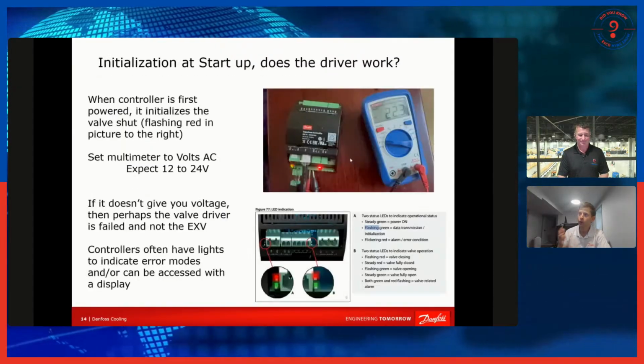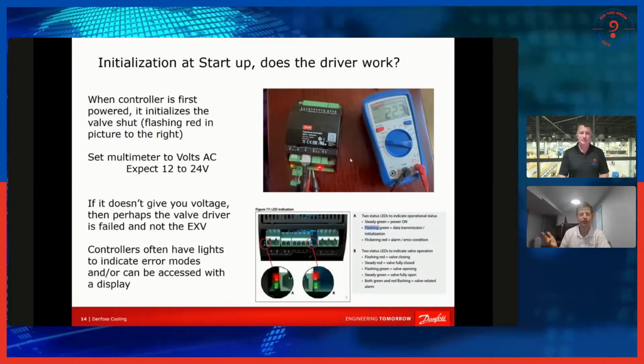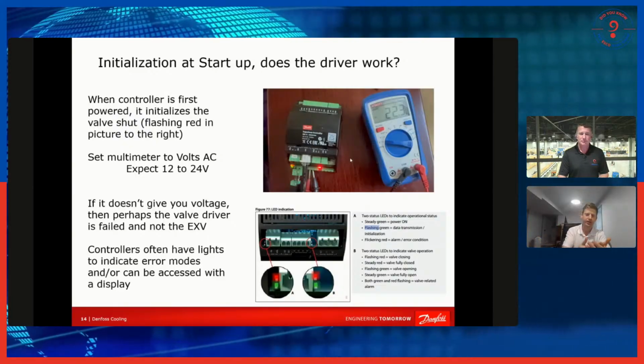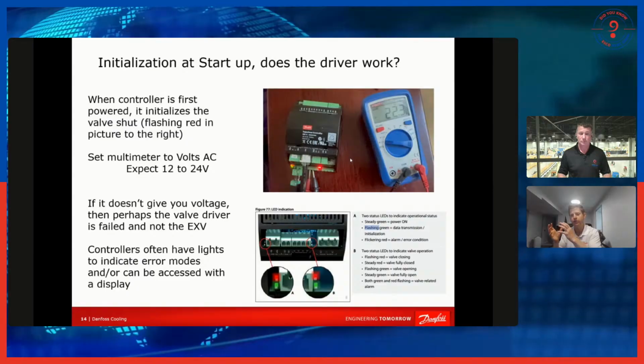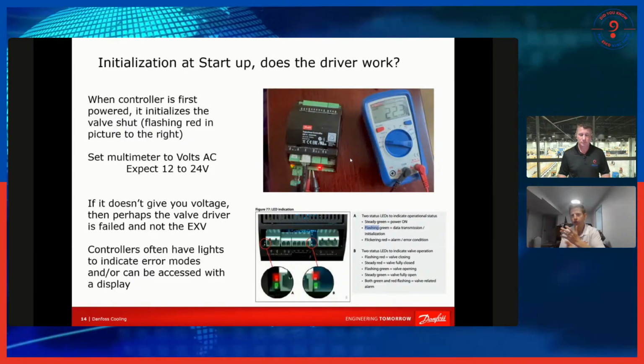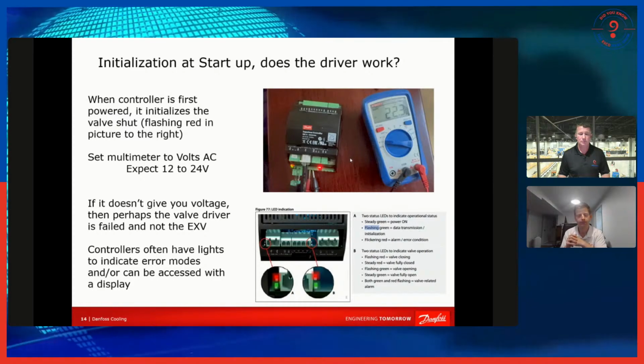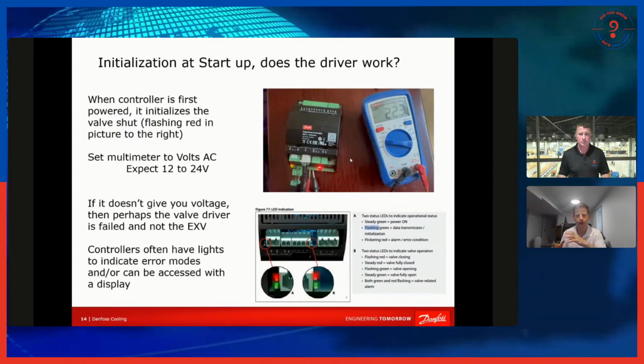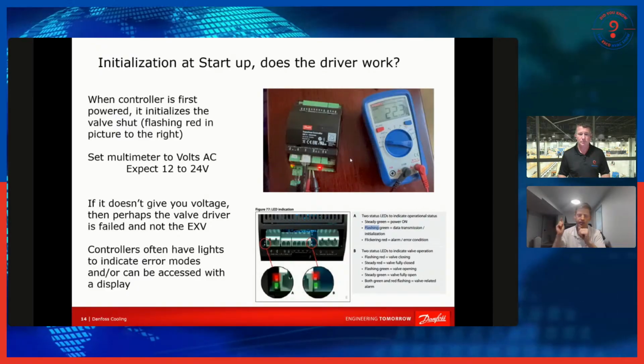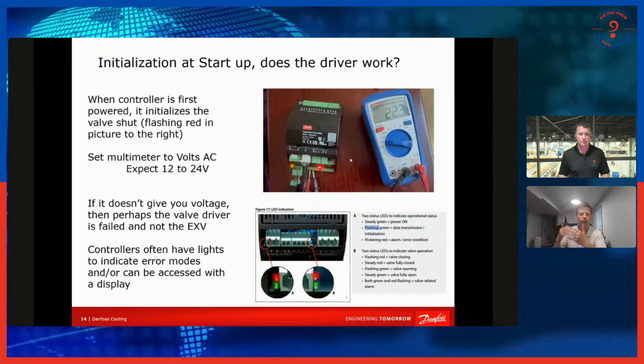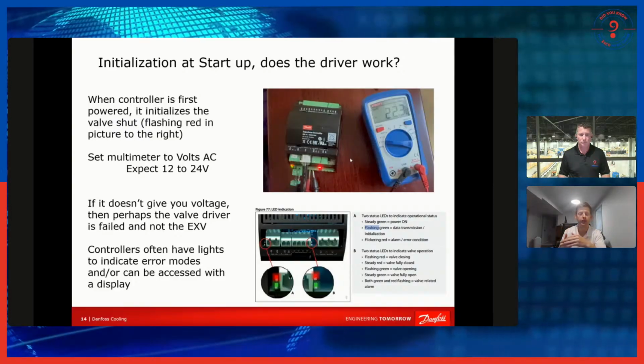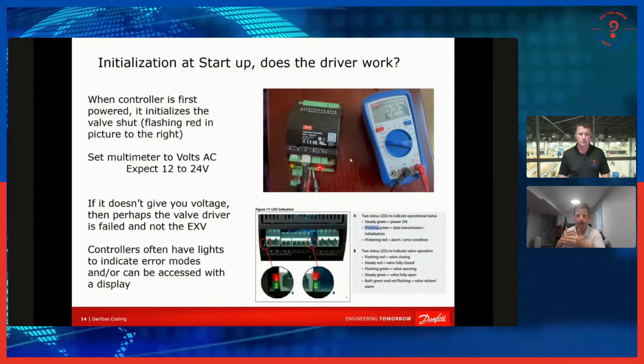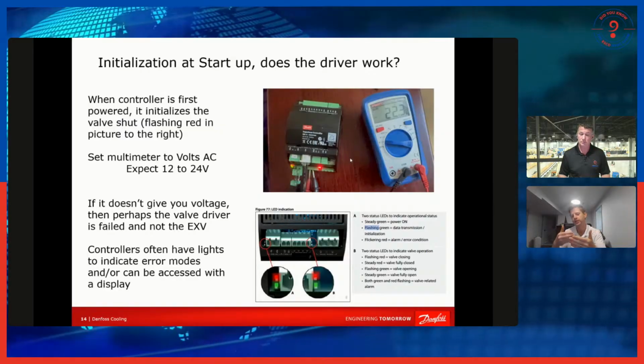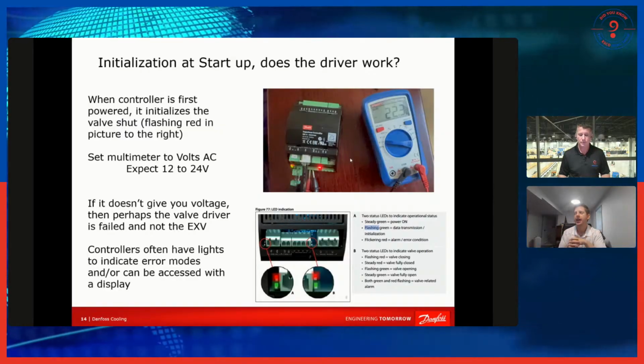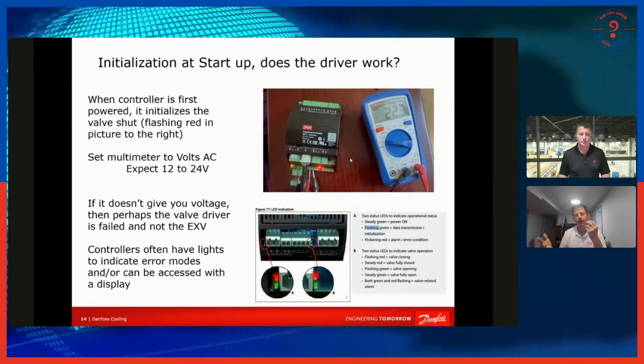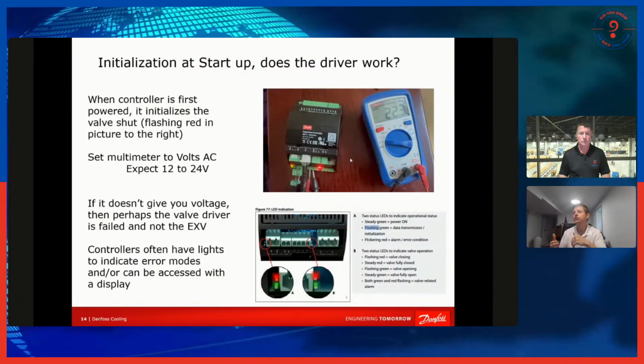That's one of the reasons why at initialization, an EXV is always driven 100% closed: when a controller doesn't have power, it doesn't know where the EXV is. Whenever a controller first powers on, there might be a few seconds where it's waking up. But once it's awake, the first thing it does is drive the EXV 100% closed, whatever the total number of steps for that valve is, and sometimes a little bit extra to make sure it's fully closed. Then it starts controlling to open to where it needs to be. This gives you a good advantage if you understand those controllers, to troubleshoot them.